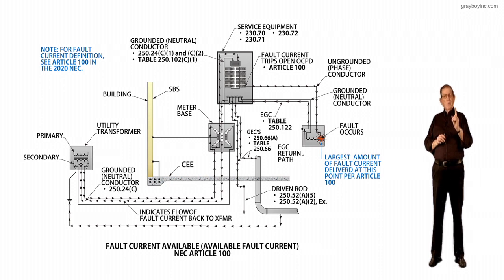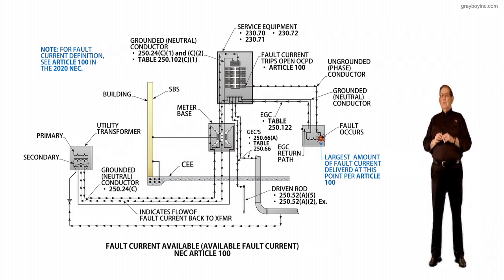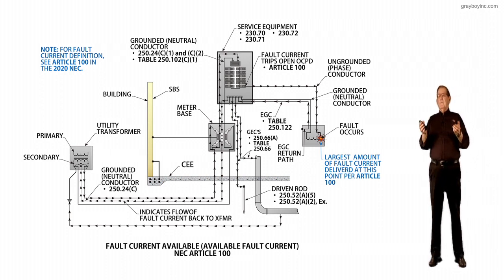But you have to compare if neutral current is involved. And naturally, you would go to 220.61, calculate the neutral load, and you can say, well, yeah, we come up with a 1-aught, 150 amp neutral load. Then you would have to increase from number 2 from table 250.102(C)(1) to the 1-aught conductor calculated for a neutral from 220.61 to have that low impedance path.